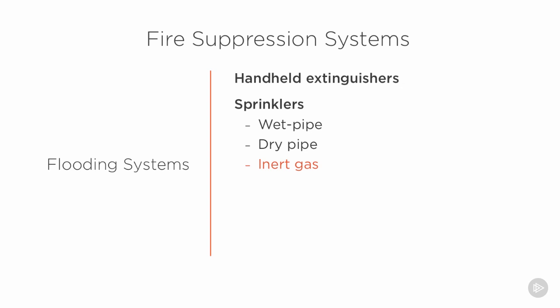Now, these tend to be expensive, and of course, there is still that risk of life safety, because if I take a carbon dioxide system and I flood that entire server room to the point that the oxygen concentration is low enough not to support a fire, it could well be that it's also not high enough to support life. And if we had somebody who was injured in that server room, it could well be that they would not be able to be rescued in time.